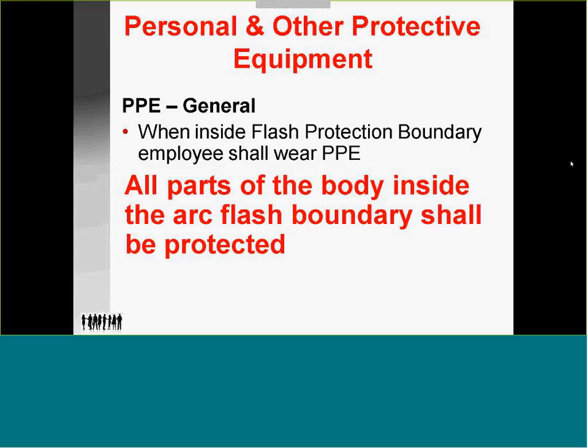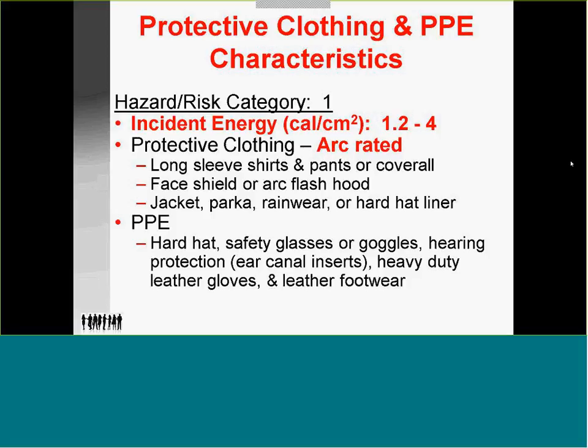Inside flash boundaries, all parts of the body inside the arc flash boundary shall be protected. I'm repeating this for a reason, to understand there can be no bare skin. Now we go into category 1. This is approximately 1.2 calories to 4 calories. The clothing will be arc rated. Long sleeve shirts and pants or coveralls. A face shield or a hood. Now if you're working outside, jacket, parka, rain gear must be arc rated. Then PPE, a hard hat, which will hold the face shield. Now underneath the face shield, you must wear safety glasses or goggles. Hearing protection must be canal inserts. Heavy-duty leather gloves and leather footwear.